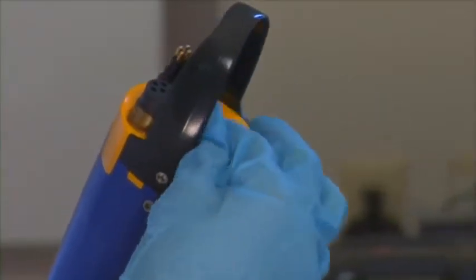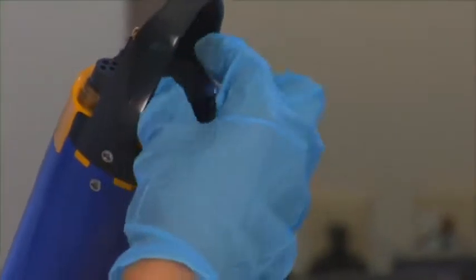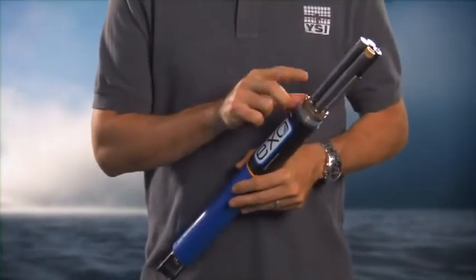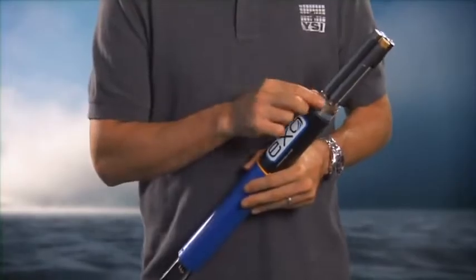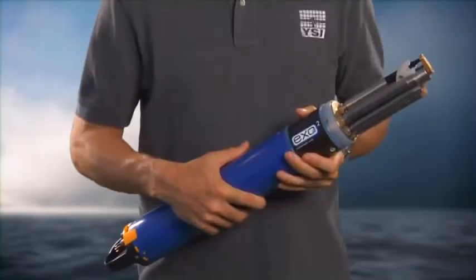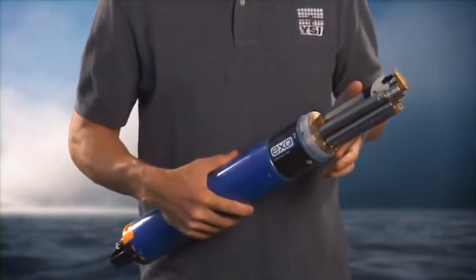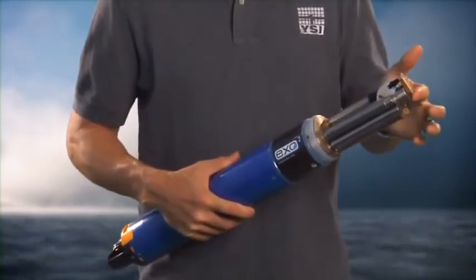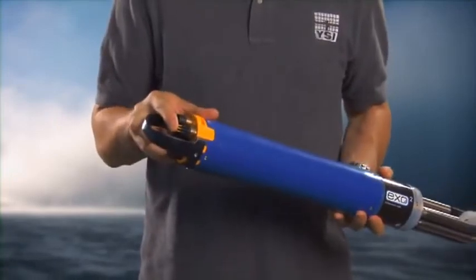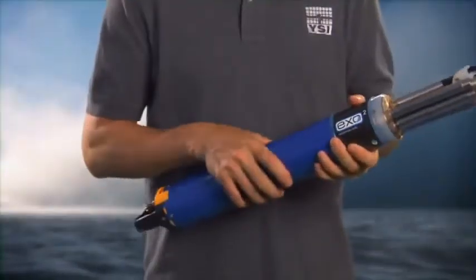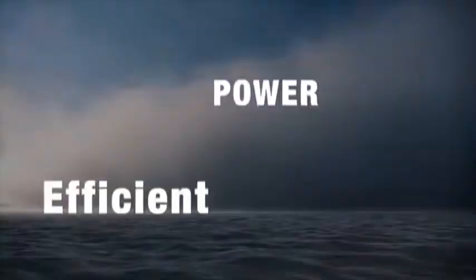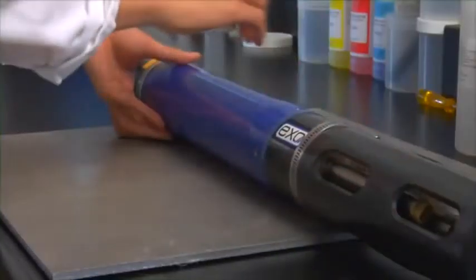The sondes are the controllers for the sensors and supply power and data logging functions. The EXO 1 sonde has 4 sensor ports and is only 1.85 inches in diameter and 25 inches in length. The EXO 2 has 6 sensor ports, an anti-fouling wiper port, and an auxiliary port to daisy-chain additional sondes or to integrate third-party sensors. The EXO 2 has a 3-inch diameter and is 28 inches in length. Efficient power management. The sonde's low power consumption and advanced power management allow you to keep it continuously deployed for approximately 120 days at a 15-minute sampling interval on a single set of batteries.